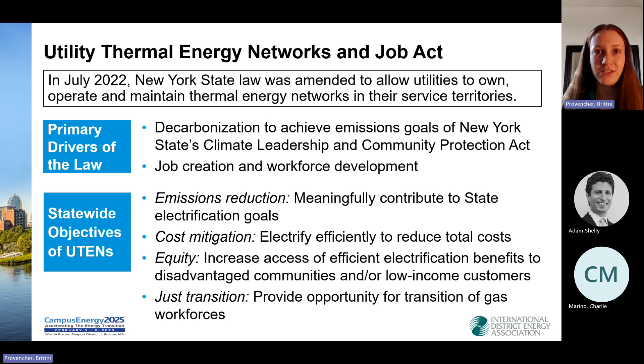A UTEN is a district energy system, but one that's owned and operated by a utility. Most of the time, district energy systems go hand in hand with geothermal applications. However, installing boreholes in a large, dense city like New York City can be a challenge. UTENs can use other heat sources and sinks than geothermal boreholes, like waste heat captured in condenser water and chilled water plants.